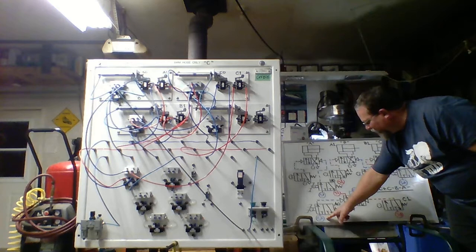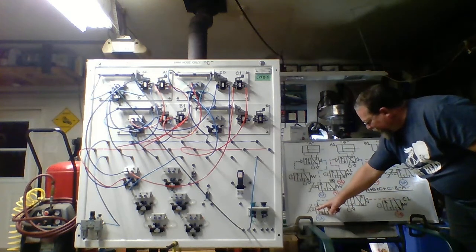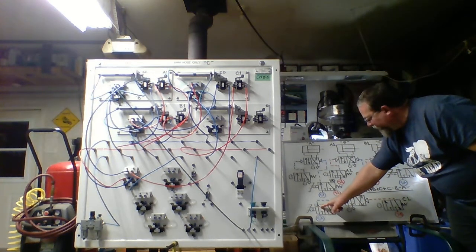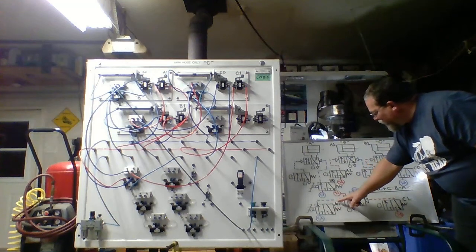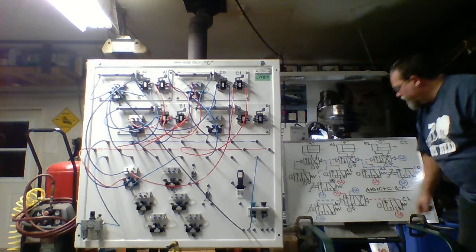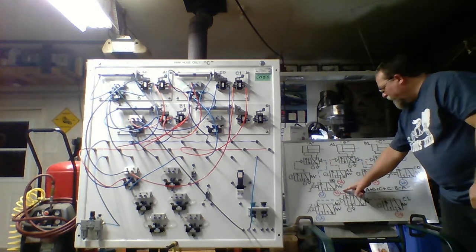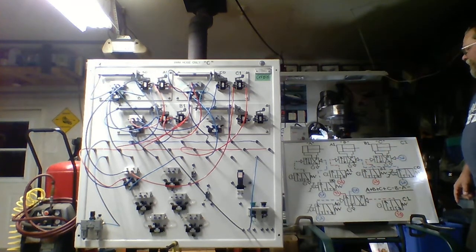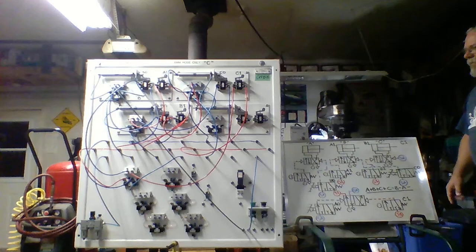Looking down the bottom here, you can see A0. We still have source 2 available. Again, the setup is the same as B0 and C0. We look at our flow path here, and we're directly piloting the cascade valve to shift it from left to right. And when we do that, we're back to source 1. So at this point in time, we're ready to start over. Everything is where it should be in home position.